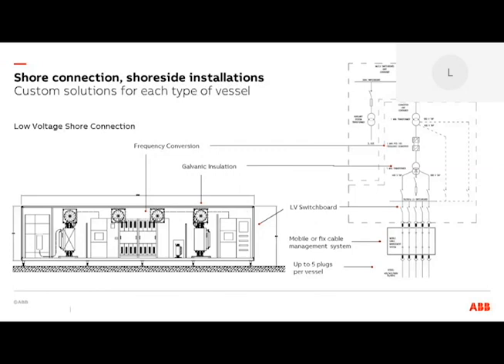In low voltage shore connection, the decision is to have a different and more flexible solution. So whatever the type of vessel, it will find on shore a flexible facility with 1 or more plugs, up to 5 plugs, that is able to deliver up to these 3 standard voltages, the 400, 440, and 690 volt, and the 2 different frequencies, the 50 and the 60 hertz. The vessel will connect only with the number of plugs that it actually requires.